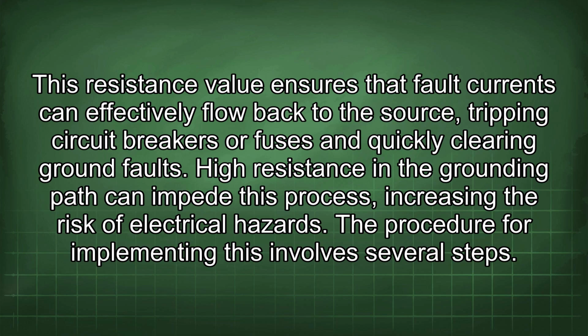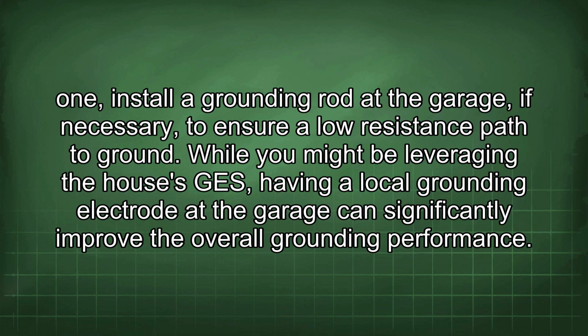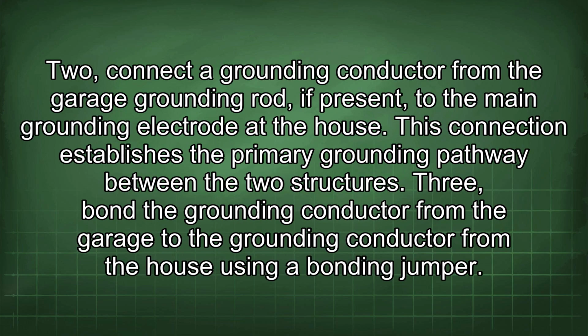The procedure for implementing this involves several steps. 1. Install a grounding rod at the garage, if necessary, to ensure a low resistance path to ground. While you might be leveraging the house's GES, having a local grounding electrode at the garage can significantly improve the overall grounding performance. 2. Connect a grounding conductor from the garage grounding rod, if present, to the main grounding electrode at the house. This connection establishes the primary grounding pathway between the two structures.